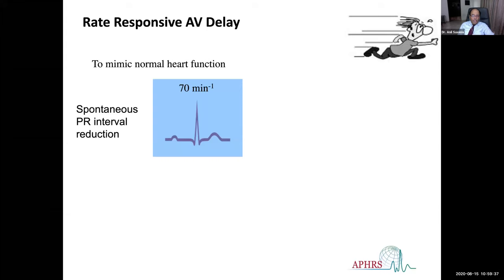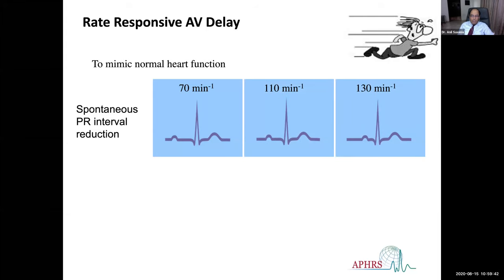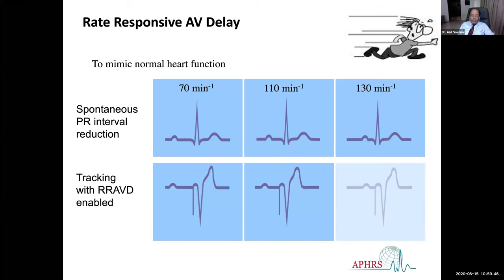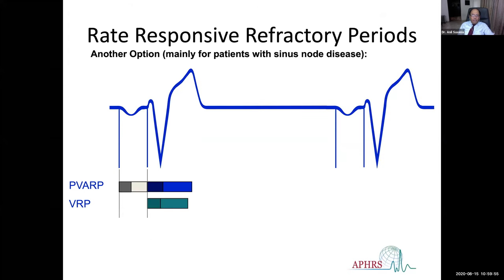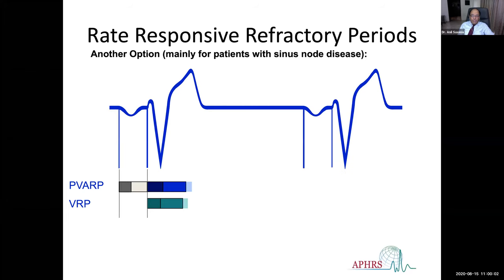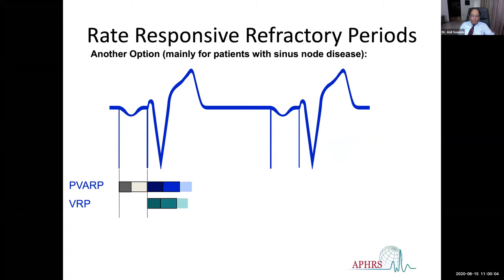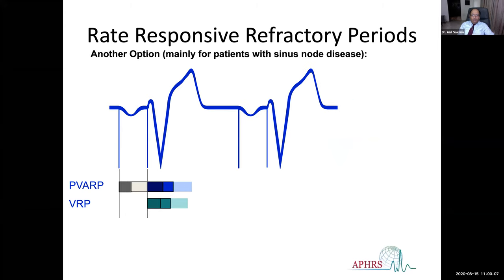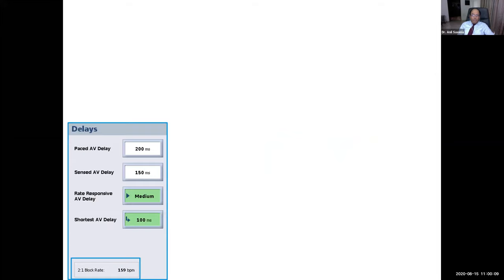We all know that as we increase our heart rate, the AV delay gradually shortens, the PR interval shortens. The same thing can be programmed to be mimicked by the pacemaker, that with increasing heart rate, the pacemaker will shorten the AV delay, allowing a higher tracking rate. The same can be done with the PVARP, that at low rate the PVARP is longer, but as the heart rate increases, the PVARP may reduce, allowing a higher tracking rate. That's how we can program it.